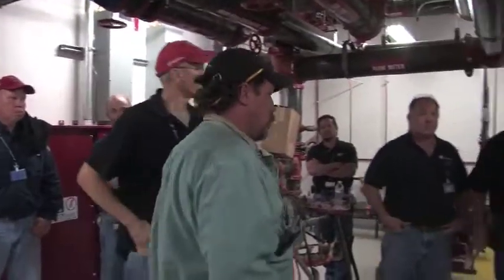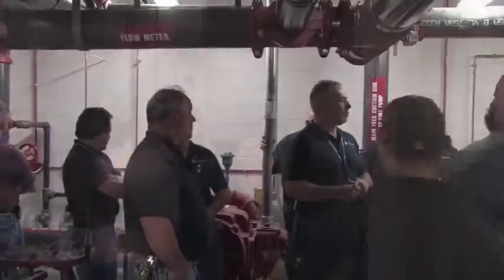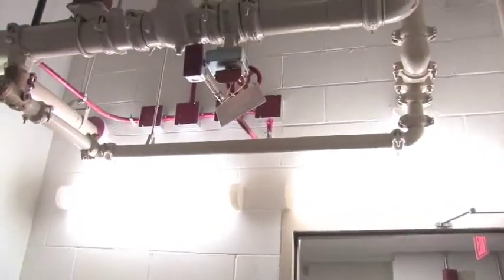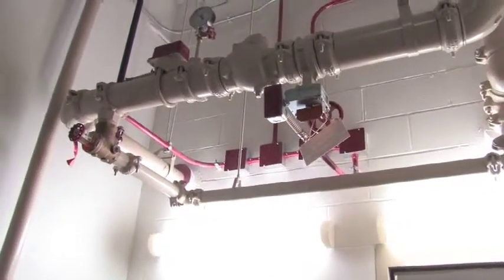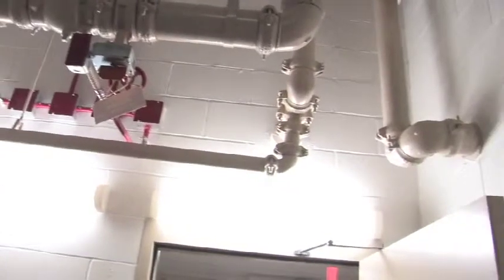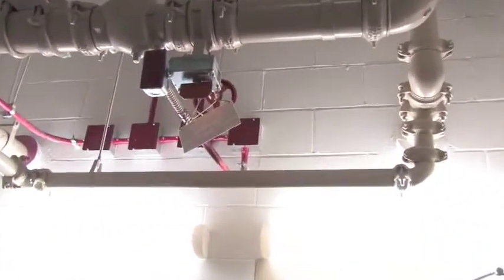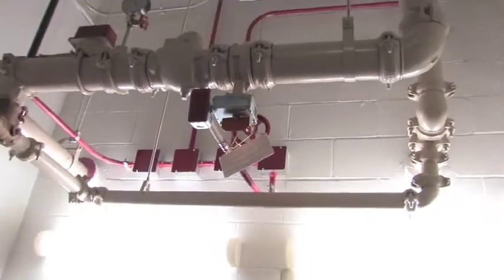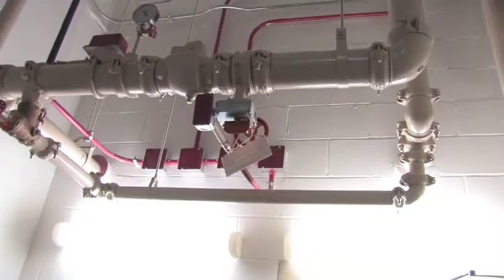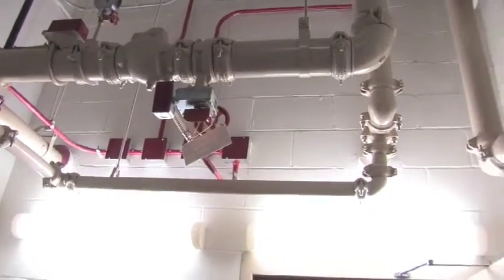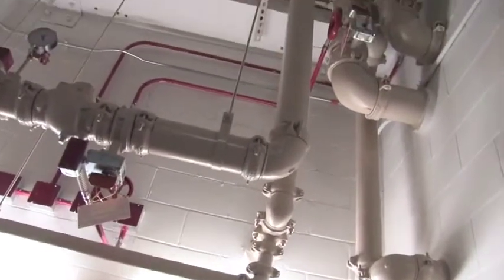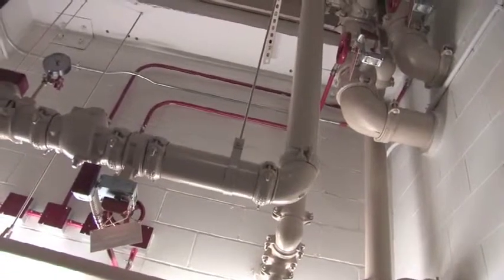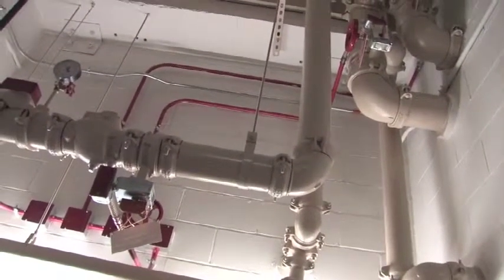Let's take a walk outside here and I'll show you where the valves are on this one. They're informative. They tell you, for instance, what it's doing and what you have to do to kill the riser, and especially for these floors. So this valve is one of the two valves that you have to shut off to service the sub-basement sprinklers right down here. There's another valve in the stairwell over there. And right on the tag, it's going to tell you that this is one of two valves you have to shut off. So they took the guesswork out of it, unlike the old days, you know. So I like that. And right up there, one's high zone, one's low zone. The higher one is the high zone, and the lower one is the low zone. But it says it right on the tags.